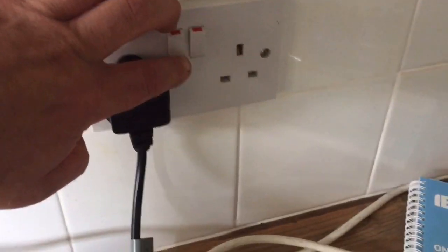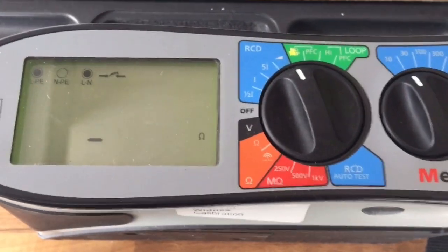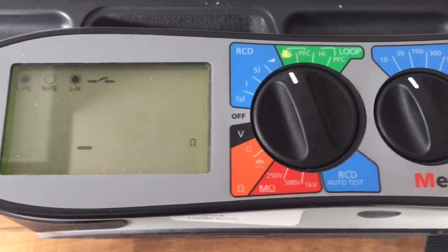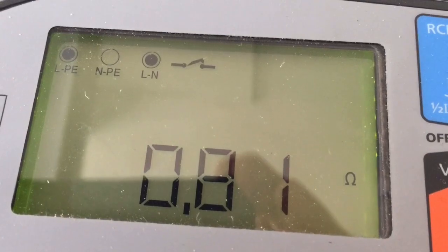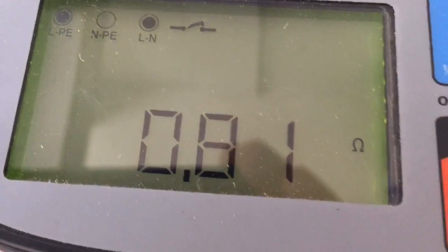Let's go ahead and take the test. Here we go — it's on no-trip loop, it takes a while. 0.81Ω — so that's a pass, because what we were after was 1.1.